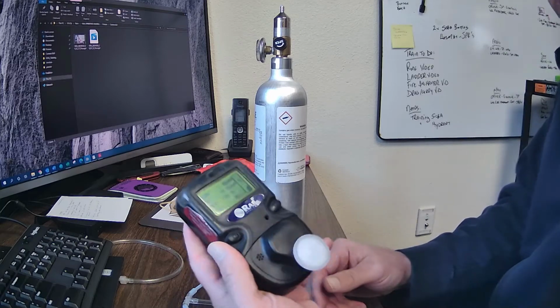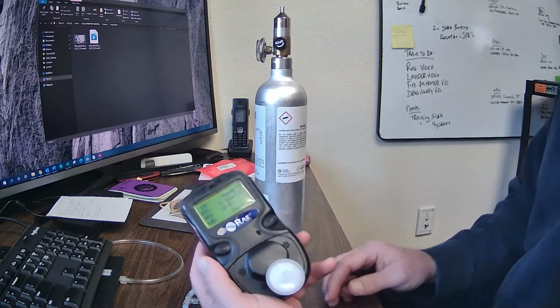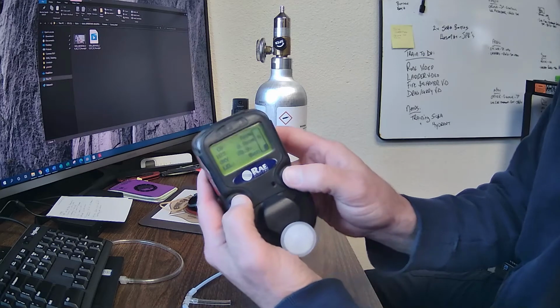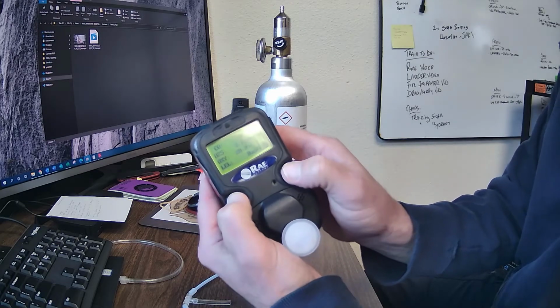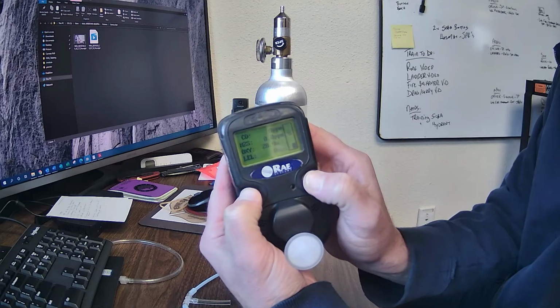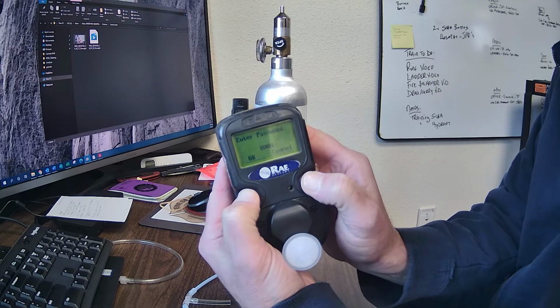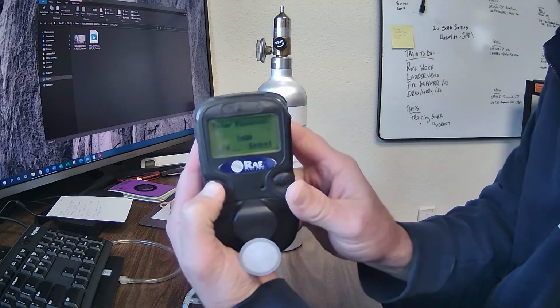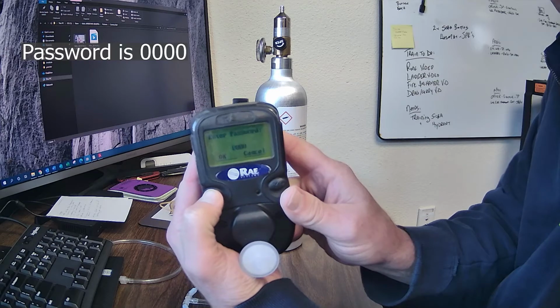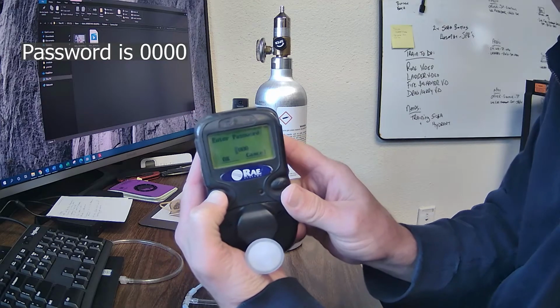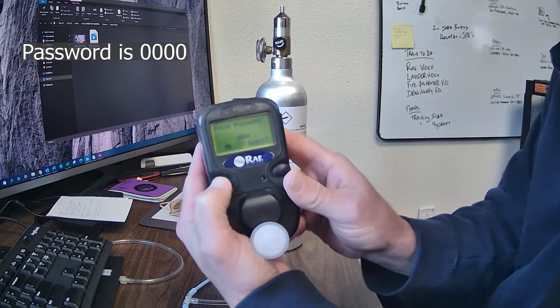Now we're going to go through the calibration for the QRae 2. The first thing you have to do is hold both these buttons at the same time. A little bit of coordination, but not much. And then you have to select the password. The password is 0000. That's the password for all our units.